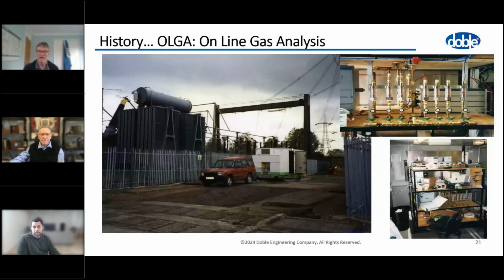The main concern I had was that the transformer we were examining was a 750 MVA transformer, a stretched 500 MVA design, and it overheated substantially. To analyze the oil, I had to take it out of the main tank into my little examination cabin, the white thing, which I'd call a relocatable DGA device, not necessarily portable, but relocatable, where we did lots of analysis and experiments with all the available devices on the market, plus our own.